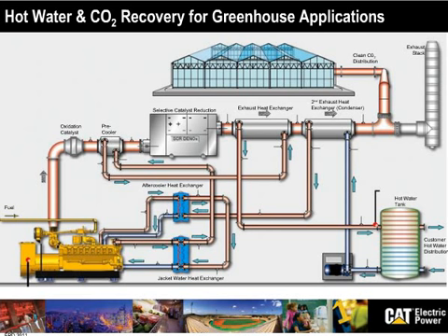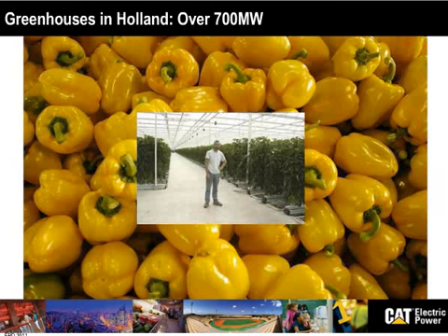Typically in greenhouse application, the power is sold to the grid here in West Europe. In Russia, however, the power is sent to the lights to light the greenhouse, and the CO2 and the heat is used to keep the greenhouse warm, of course. The most successful place where we have greenhouse application is Holland. In Holland, we have 700 megawatt installed, extremely popular. We started that in the early 80s. We have more than 500 catalysts installed to date, and 3,500 gas gensets have over 100,000 hours as we speak.